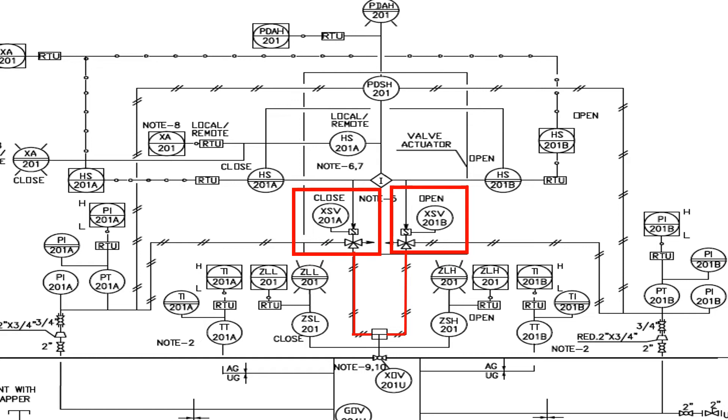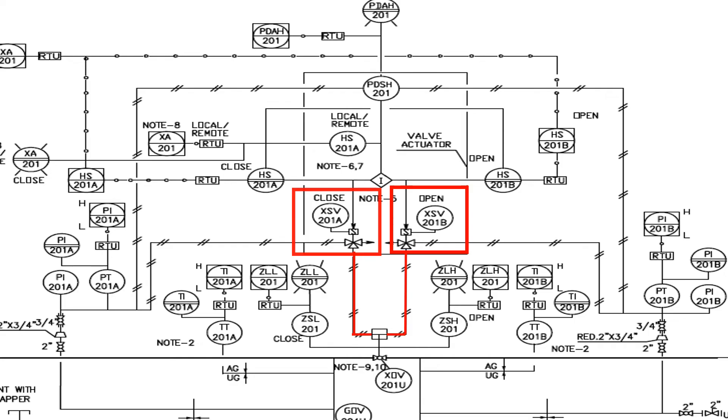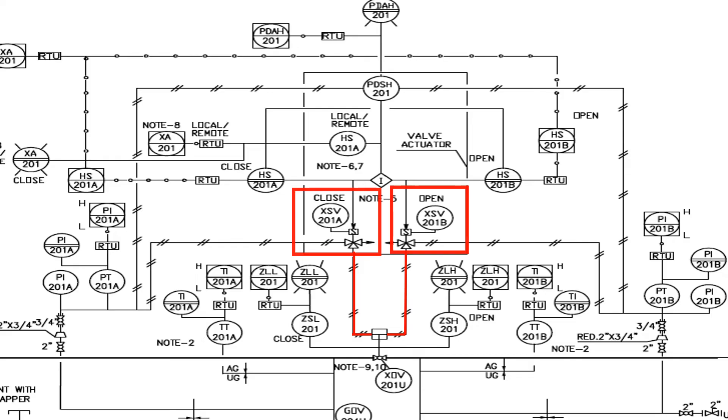When we follow this pneumatic lines, we can see two solenoid valves from where the pneumatic lines are coming. As close is mentioned near to XSV201A solenoid valve, this valve is used to close the XOV valve. As open is mentioned near to XSV201B solenoid valve, this valve is used to open the XOV valve.